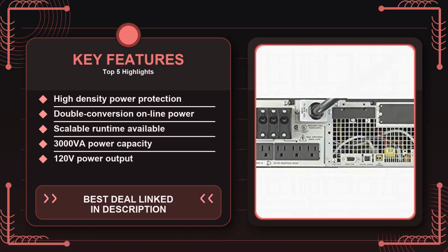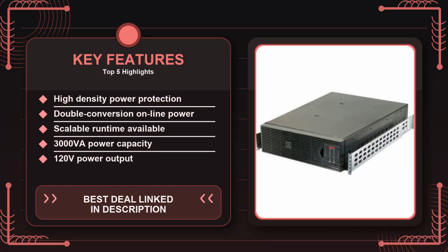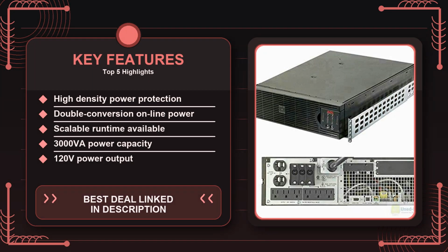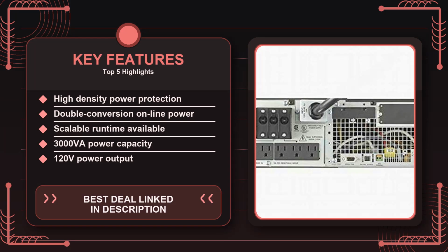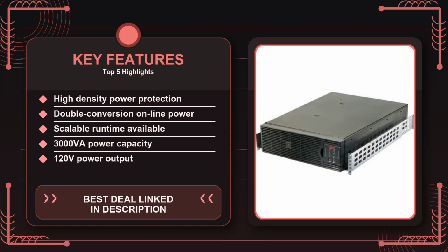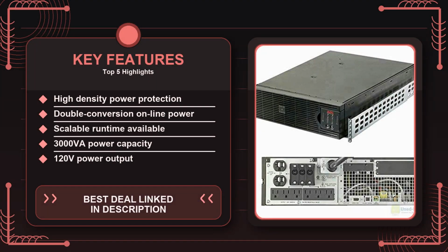The APC SURTA3000RMXL3U 3000VA Smart UPS RT sits right in the middle of that decision curve. It's marketed as a high-density, double-conversion, online UPS that can be mounted either as a rack unit or used in a tower configuration. That flexibility is attractive for small to mid-sized data centers that might have a mix of rack space and freestanding equipment. But does it actually deliver on the promises when you plug it into a real-world setup? Let's break it down. First, who should consider this machine?